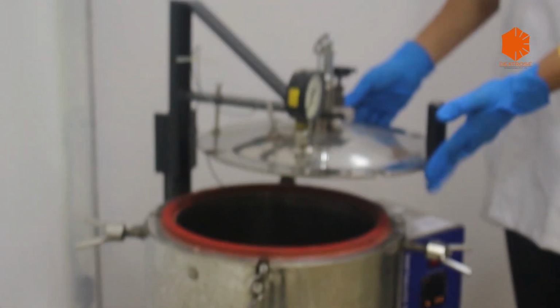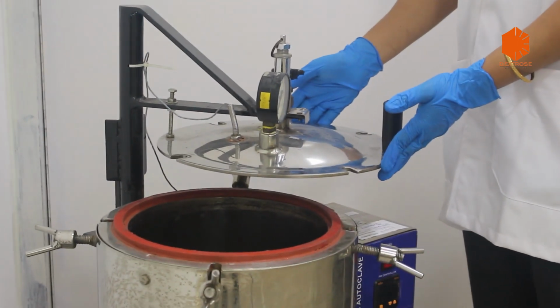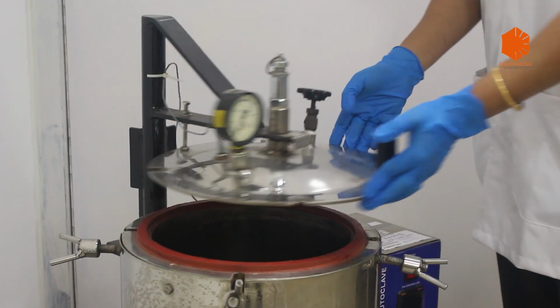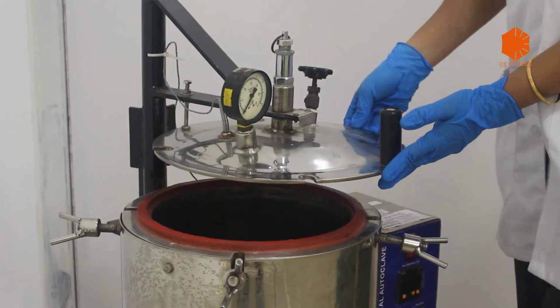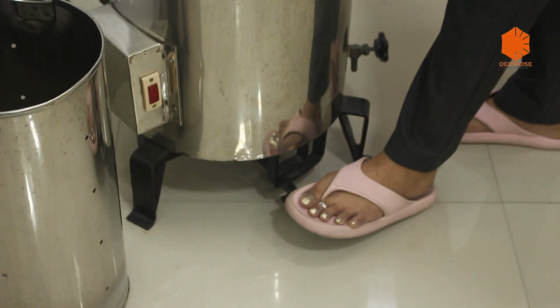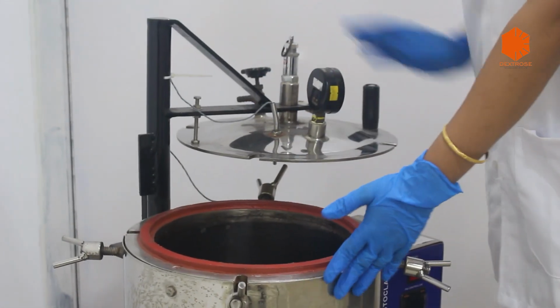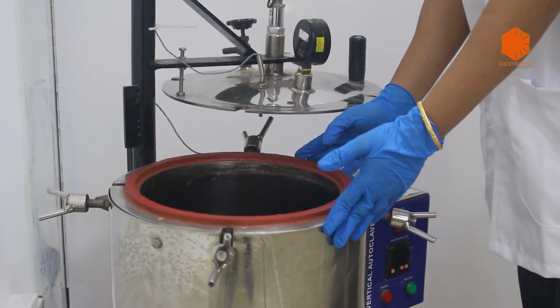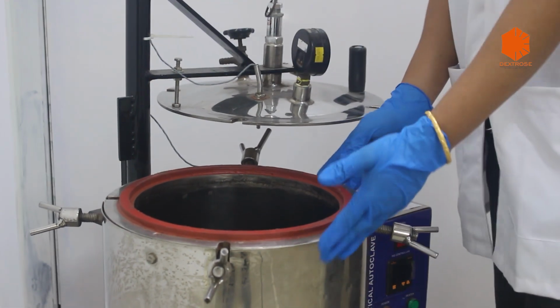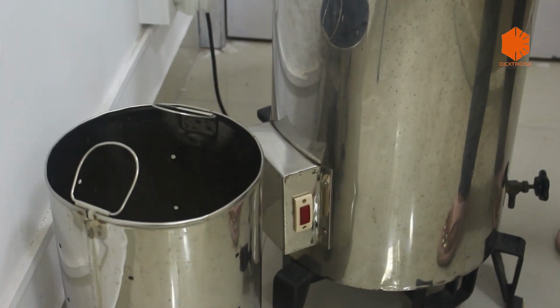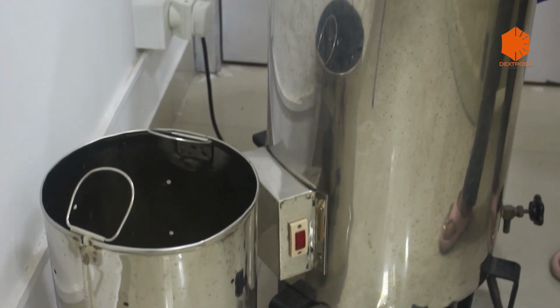So an autoclave comes in different varieties. The one which I'm going to show you now is a vertical autoclave. So what you can see here is a vertical autoclave which you can most commonly find in laboratories in colleges and other facilities. So this is the lid which can be operated with the help of this pedal here at the bottom. Okay, and this is the pressure chamber which is actually double walled, made up of stainless steel, and here what you can see is the basket into which the components which are going to be sterilized go in.